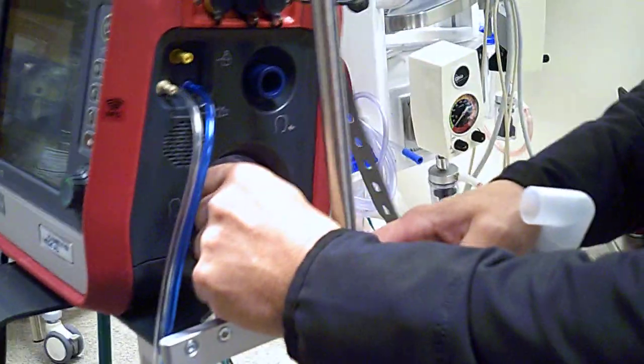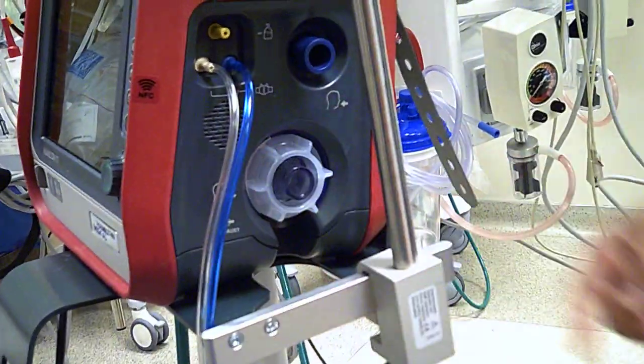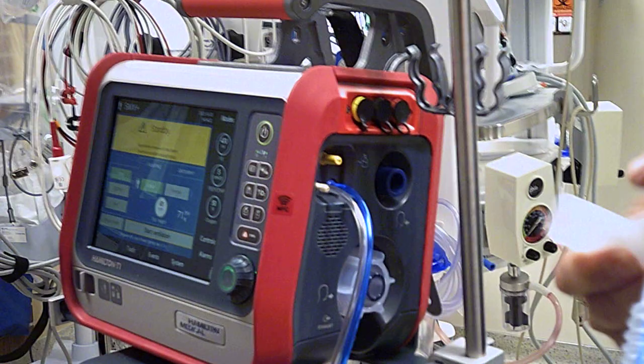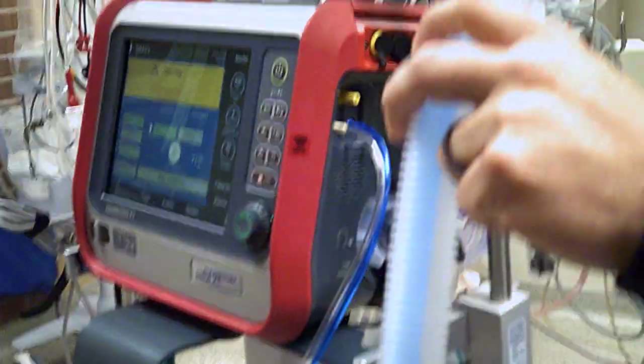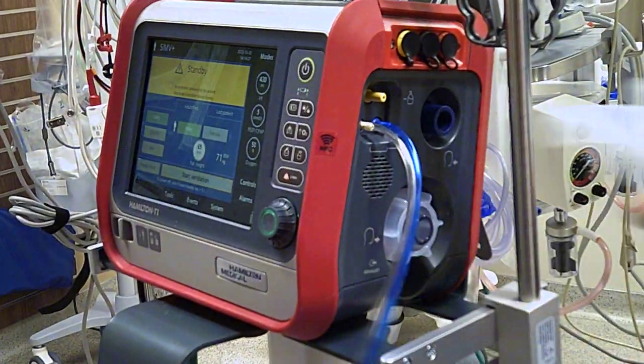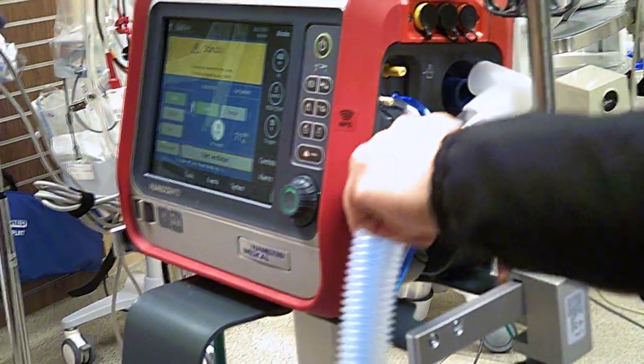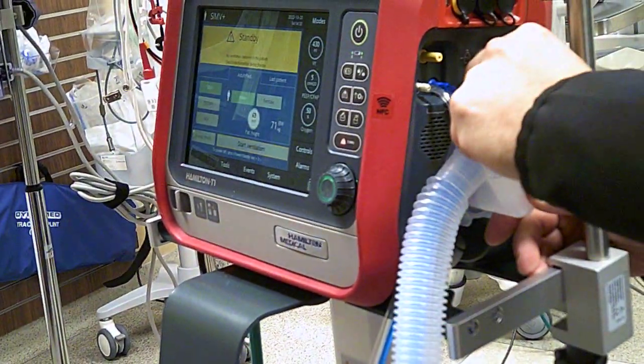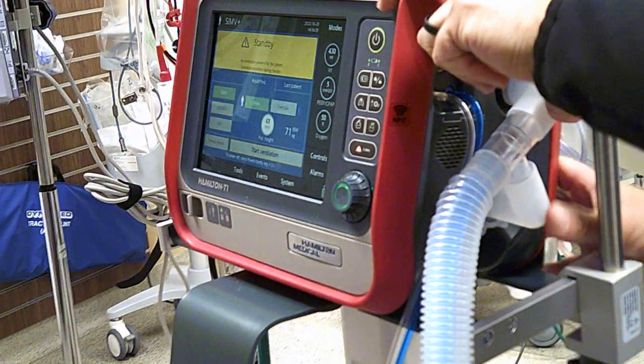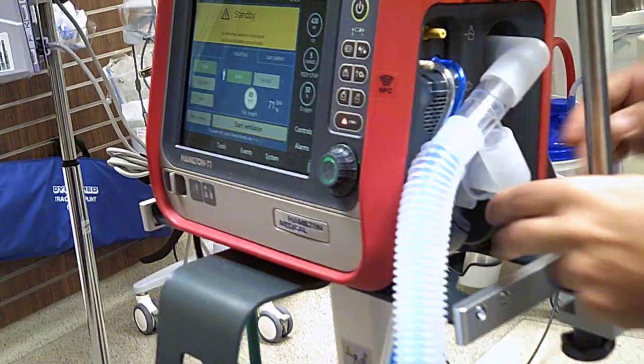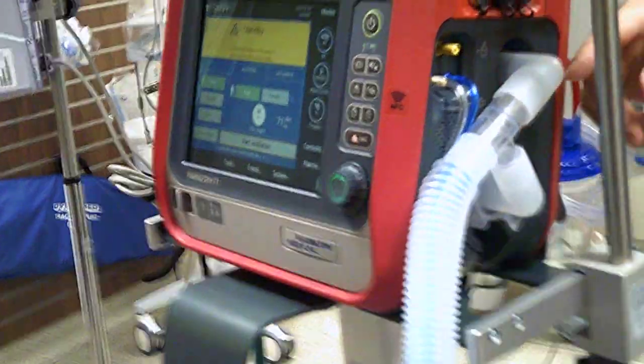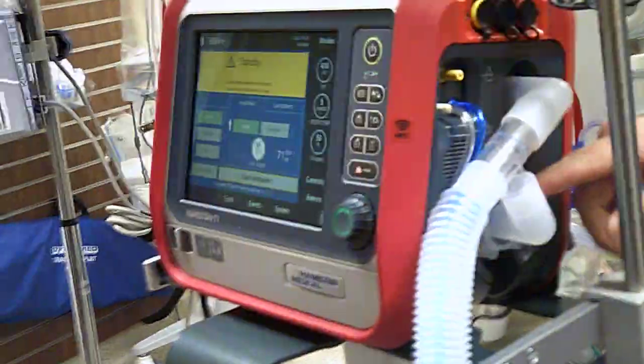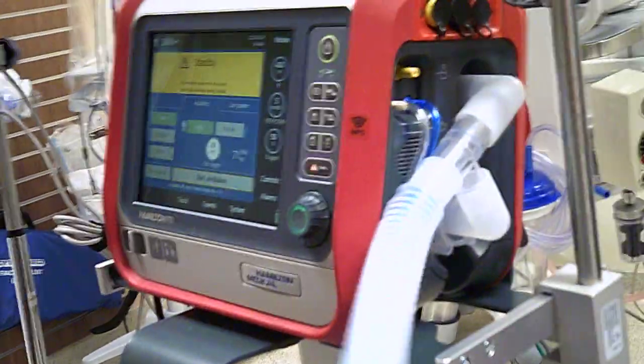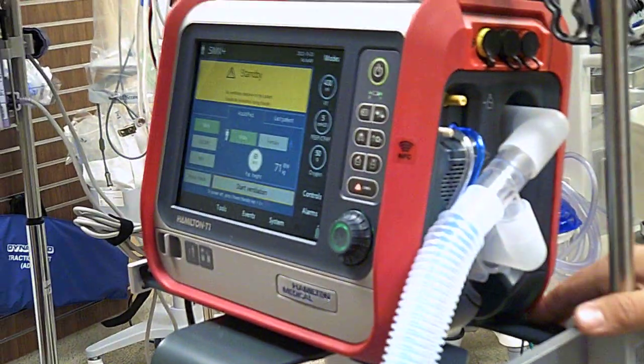This part goes down and then twist to the right. It's locked in there, you're good. These, it doesn't matter, you can connect it this way. I normally do it so it faces out, which makes more sense to me. Make sure these are tight, because when you do your flow tests and all that, this is a common area where you're gonna get a leak. And if the diaphragm isn't there, it'll fail, or if you have a different diaphragm in there.